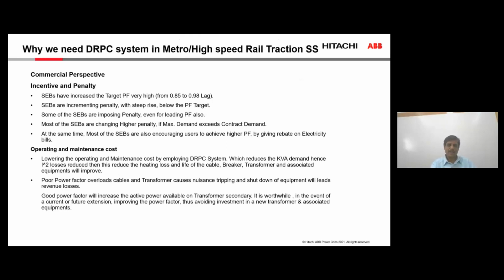And then the availability. Good power factor always means better availability of the station, and we also look at the transformer capacity getting released because of the reduced load current. We can also connect more load to the same transformer rather than going on adding new transformers. So we are able to use the existing assets for expansion or expanded load. This is a huge thing.